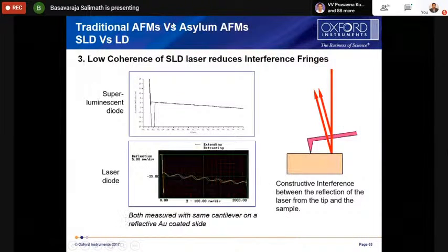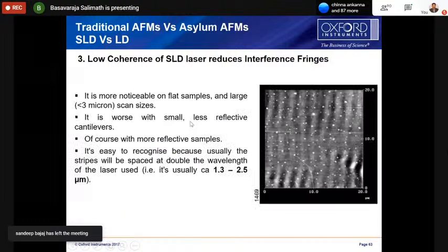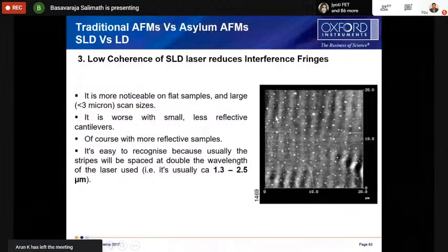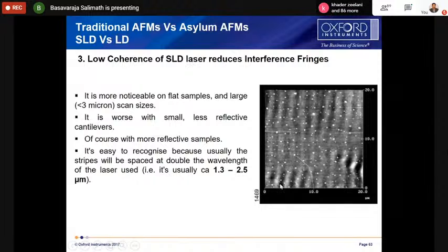Also, we use SLD lasers, whereas many other traditional AFMs use a normal visible light laser; we use an IR SLD laser. What happens is that when you align the laser at the end of the cantilever, a small amount of laser also falls on the sample. The laser reflected from the cantilever and the laser reflected from the sample both go to the photodetector, and interference happens. Interference patterns come, so if you are doing FD curves, you will get these patterns in the FD curve, whereas with an SLD you won't. Even in imaging, you get these interference patterns if you are using a red laser or other visible lasers, but with the IR SLD laser you don't get these fringes. In our Oxford AFM, we provide SLD lasers only.